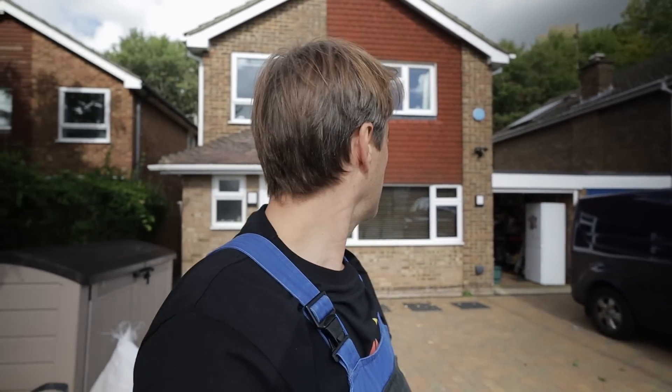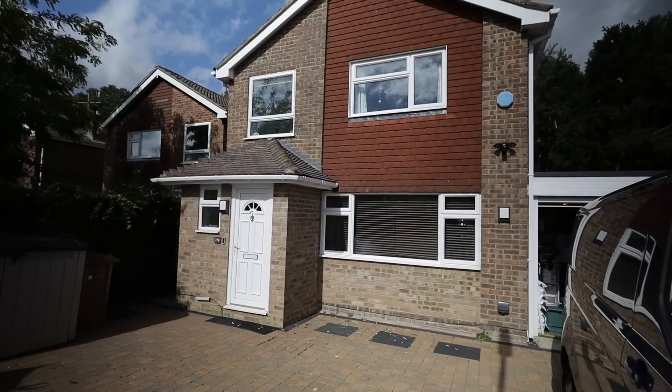What you see behind me is the property I'm working on — fully detached, four-bedroom house, originally built with uninsulated cavities. The heat loss of that property originally, with double-glazed windows already in place, would be around 8 kilowatts. By insulating all the walls and replacing the original double glazing with a better quality double glazing, the owners have managed to drop that heat loss to 5.5 kilowatts.